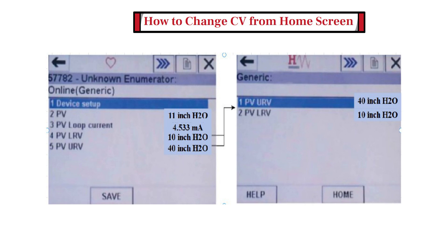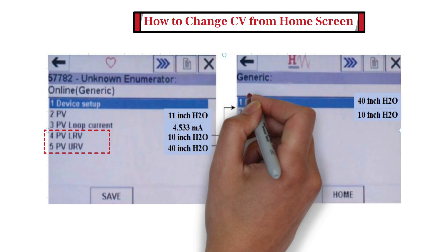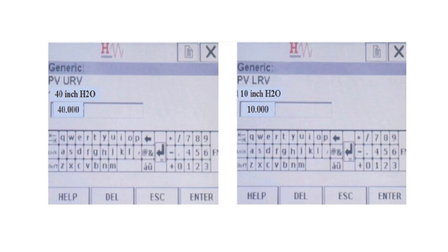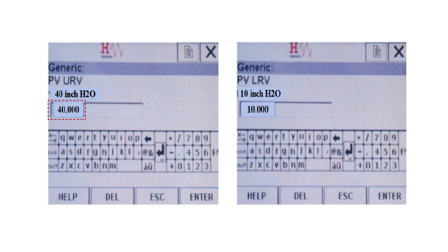First of all, let's learn how to change calibration values from the home screen. As you can see, range can be changed directly by selecting menu items PV-LRV and PV-URV from the home screen. Selecting either item will cause the communicator to display the range calibration screen as shown in the right side image. Selecting the menu item PV-URV and PV-LRV from the range calibration screen will change the display to an edit screen.